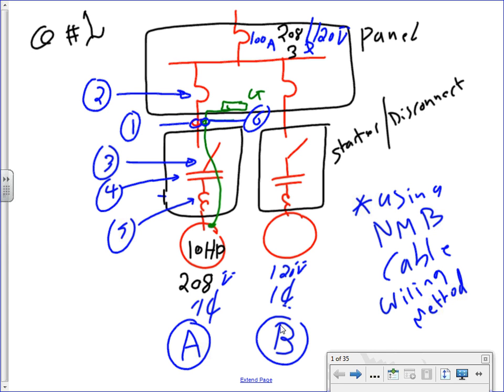Cool? We have done this example with 240/120, and now we're doing it with a 208/120 three-phase panel. We need to size these for the two examples. Any comments before we start? That's all the calculations we do, guys, is sizing. We're engineers and designers. They ask us to size conduits and conductors and so forth. So that's example number one. Comments, questions? You do have the description in front of you.